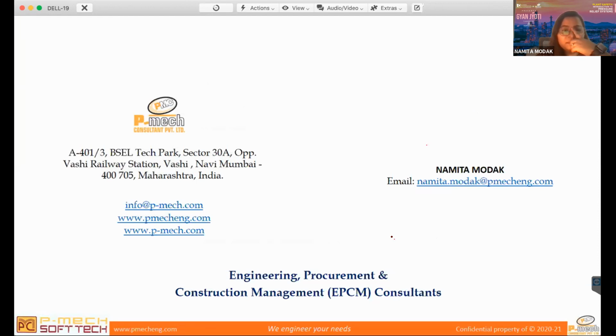Suppose in PSV calculation, if I'm getting D orifice and the client wants E orifice, at that time what to do? You can go with E orifice, because there are some clients who at the beginning of the project give the list of the type of orifice which you have to go with. So if D orifice is not in that list, then definitely you have to select E orifice. But you have to take confirmation from the vendor whether chattering is happening or not for that selection. Okay, so it depends upon chattering. Yeah, because the required orifice area versus the selected should not be much higher. There should not be a big gap between these two areas.